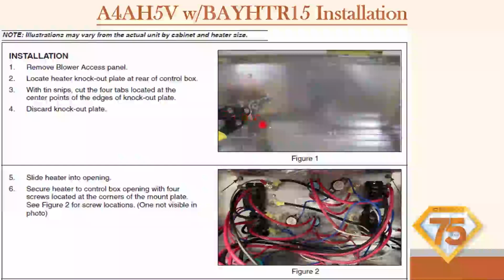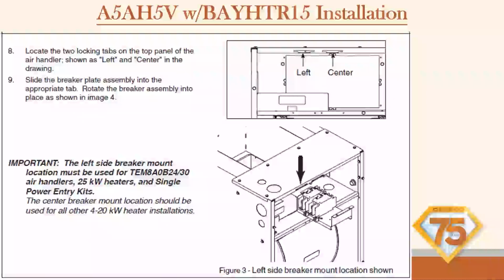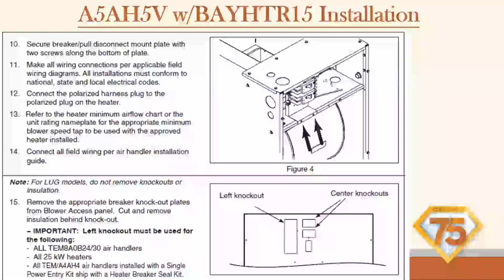A little bit different for the heat strip installation. You're gonna snip it out. You're not gonna unscrew. You gotta snip those tabs, and it only has one panel. You're gonna fit the entire heat strip in there and secure it down with the 4 screws in the pre-drill holes. You slide those breakers in, secure with a couple screws. You're going to have to knock out, if you remember, if you only have one circuit breaker in there, you will only knock out one of those plates. I've actually done that myself where I accidentally knocked out too many of them. Single point entry kit available.